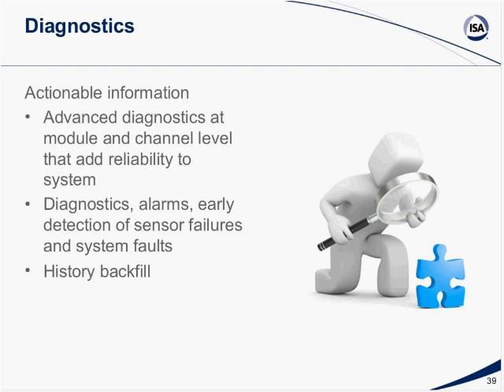It would also be good if you have a system which has the ability to provide backfill functionality, which allows your HMI to search back into the controller database and backfill the information if communication is lost between the HMI and the controller.